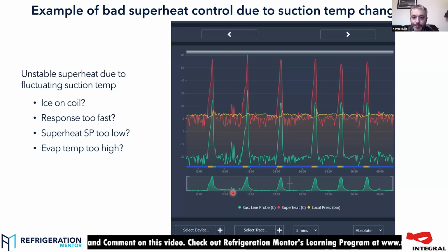This is 24 hours. As you can see on here, it tells you at the bottom what the traces are, and you can see the local pressure, which is effectively your evaporating condition, is pretty stable on that trace. But the suction temperature, when you compare it to the superheat, which is the red line, you can see the suction temperature is what's causing the superheat to fluctuate. Obviously, your big spikes are defrost. Yellow on the bar at the bottom is your defrost. But something is causing that suction temperature to be unhappy.